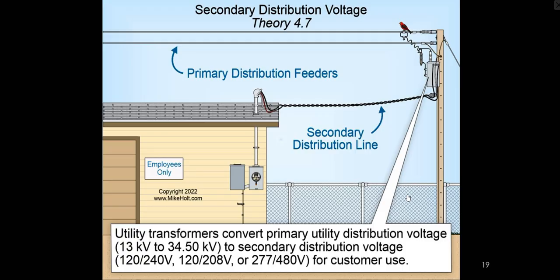Now, why is it 277 instead of 266 or 260? The utility companies are required to send what we would call the nominal voltage rating, but I like to use the term tolerance. In other words, if you understand tolerances, it's plus or minus. It could be a little bit less than that. It could be a little bit more than that, but it has to be within this window.